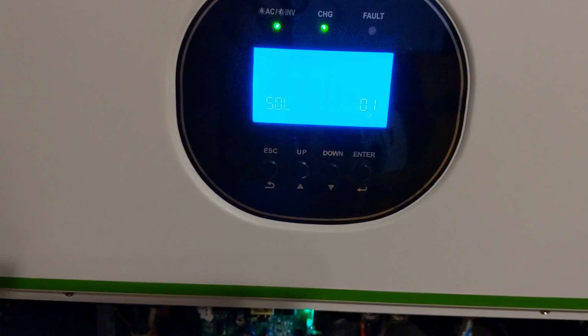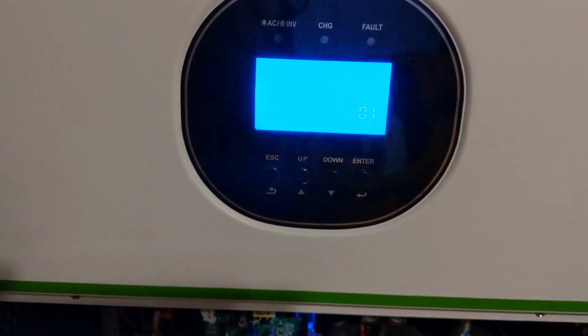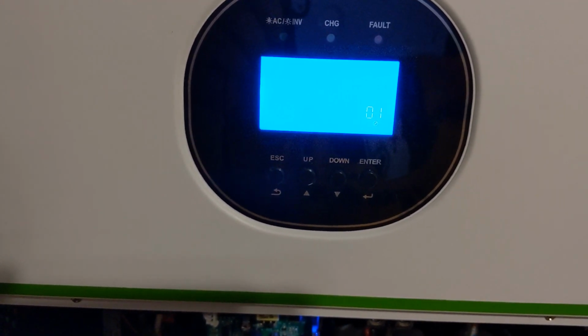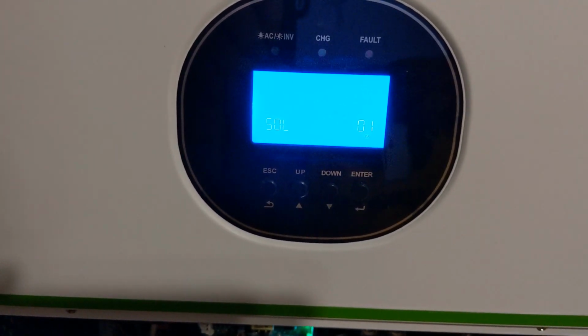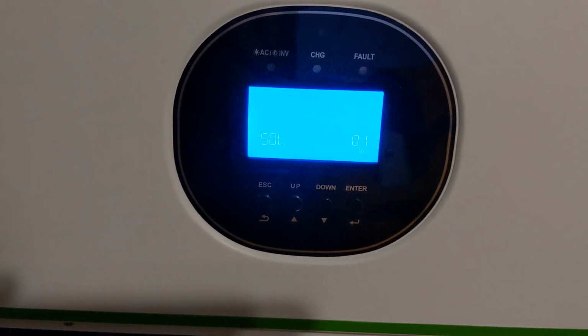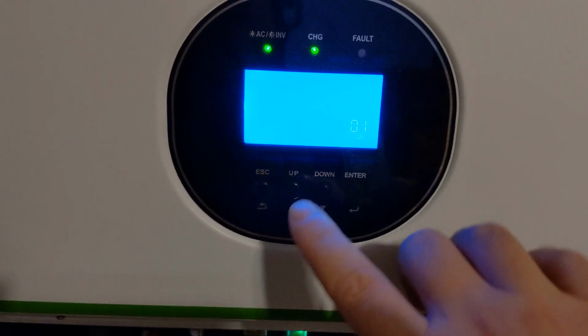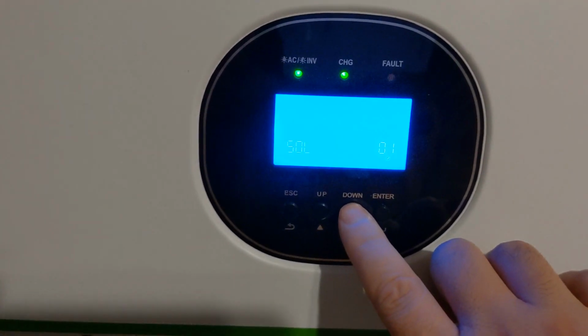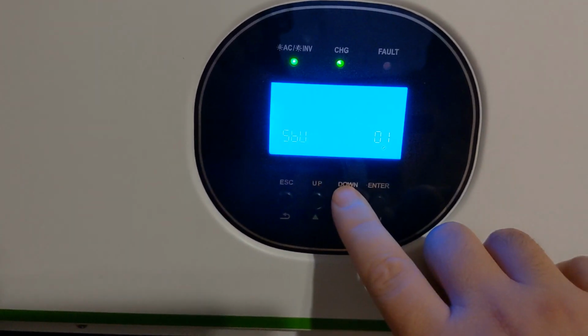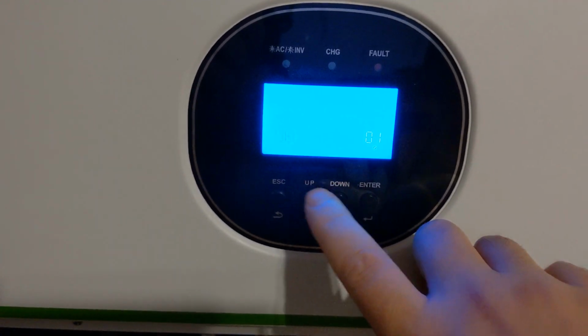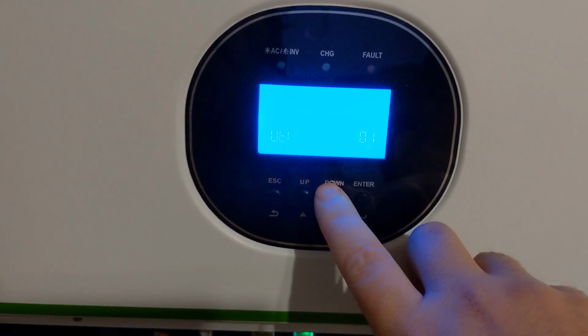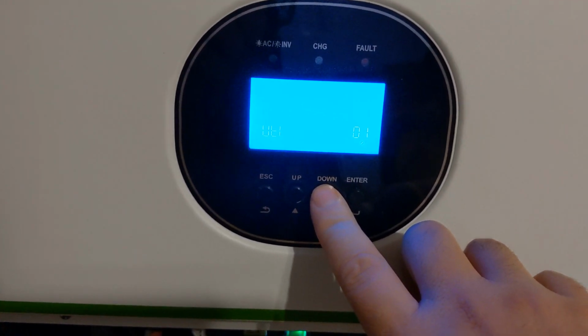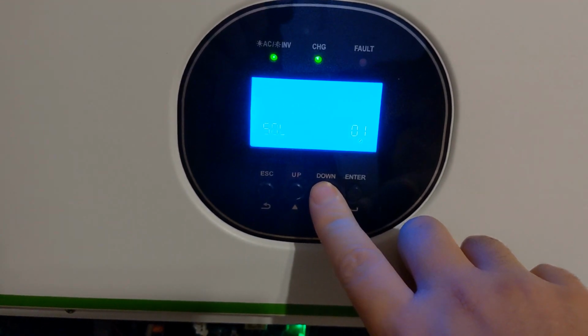That's a handy mode if you want to preserve a certain amount of battery power in there above what you normally would, because then it'll basically, for a fact, switch back off the grid no matter what your battery level is at the end of it. But it's a unique mode, to say the least. So the UE1, that one there prioritizes grid first. That's basically more like the UPS type mode. Don't really use that one, but other people probably would.